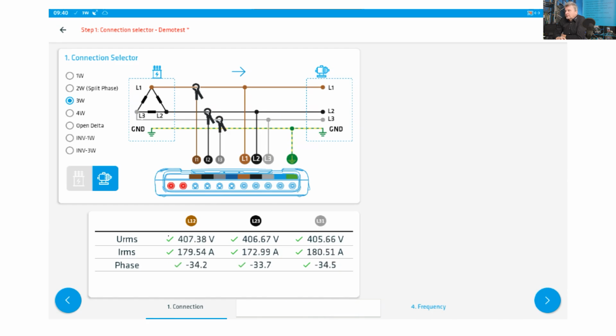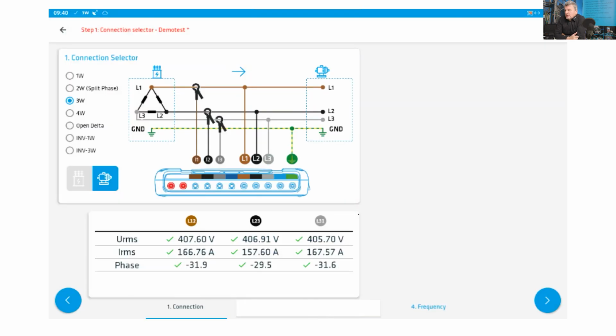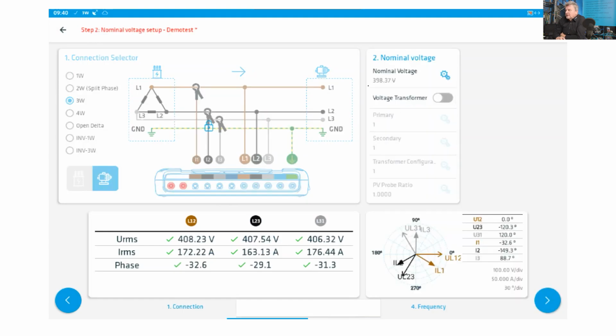Additionally, you have an evaluator of the value. With a click, you get a pop-up with the status, which is pass or not okay if the measured value is not within the specified or expected range. The next step drives you to selection of nominal voltage. You select the nominal voltage of the network, and whether a voltage transformer is used or not, for example, transferring the measurement to the primary side. Additionally, a phasor diagram is presented for easy orientation.